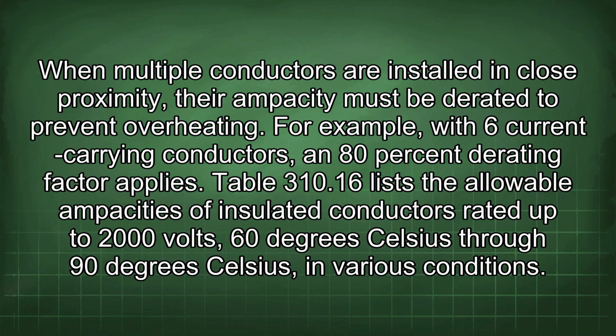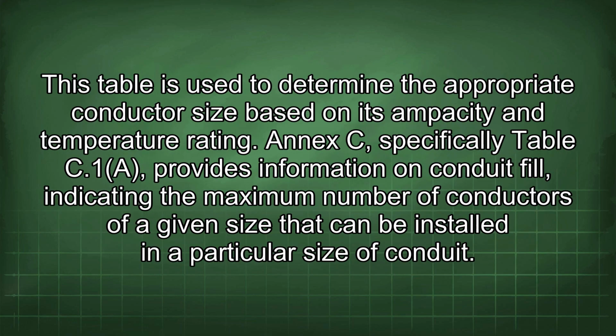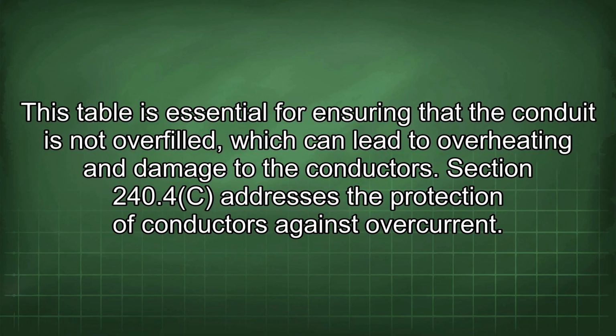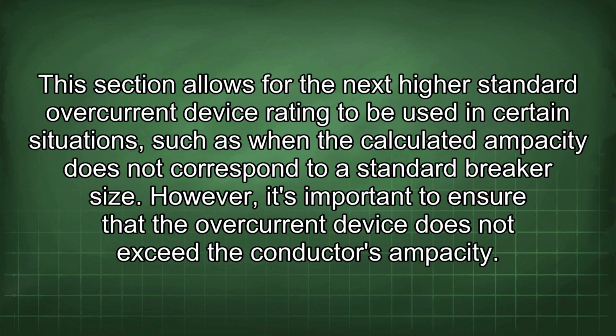Table 310.16 lists the allowable ampacities of insulated conductors rated up to 2000 volts, 60 degrees Celsius through 90 degrees Celsius, in various conditions. This table is used to determine the appropriate conductor size based on its ampacity and temperature rating. Annex C, specifically Table C.1A, provides information on conduit fill, indicating the maximum number of conductors of a given size that can be installed in a particular size of conduit. This table is essential for ensuring that the conduit is not overfilled, which can lead to overheating and damage to the conductors. Section 240.4(C) addresses the protection of conductors against overcurrent. This section allows for the next highest standard overcurrent device rating to be used in certain situations, such as when the calculated ampacity does not correspond to a standard breaker size. However, it's important to ensure that the overcurrent device does not exceed the conductor's ampacity.